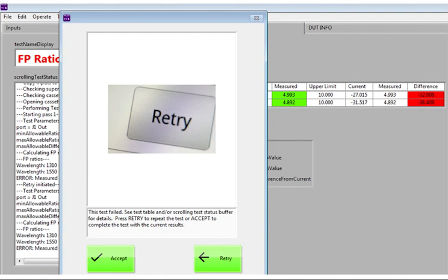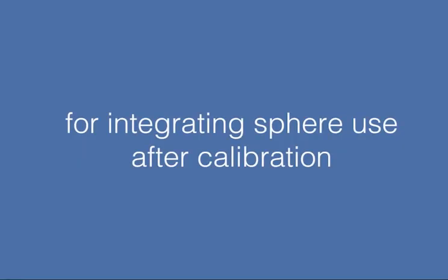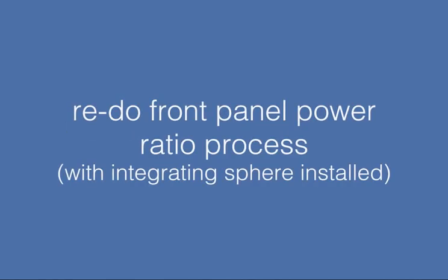If this is the case, you should accept the values measured and continue with the calibration process since the system now has the needed power values to proceed. It isn't necessary to completely start over since issues will be detected if the next steps fail. Please note, if you plan to use the module with the integrating sphere after calibration, it will be necessary to redo the front panel power ratio process with the integrating sphere installed.